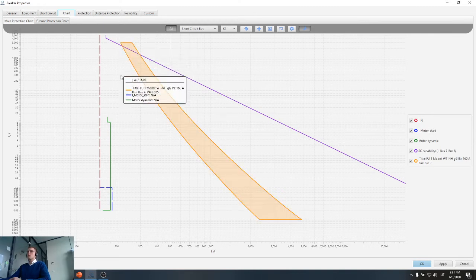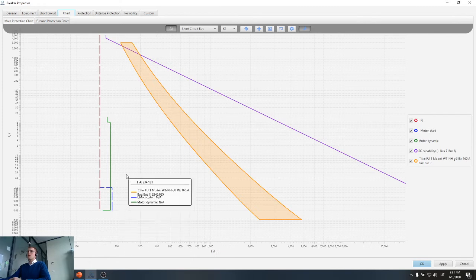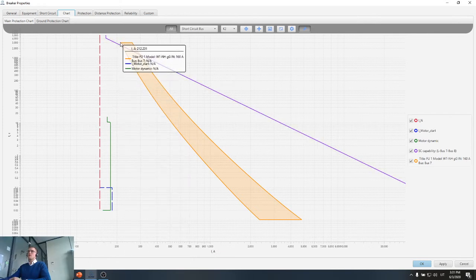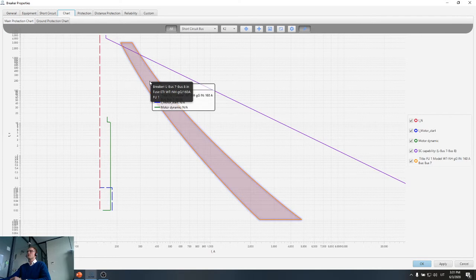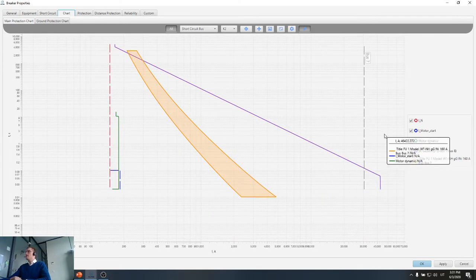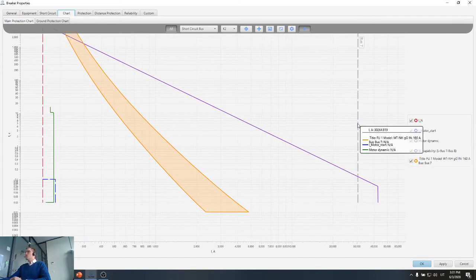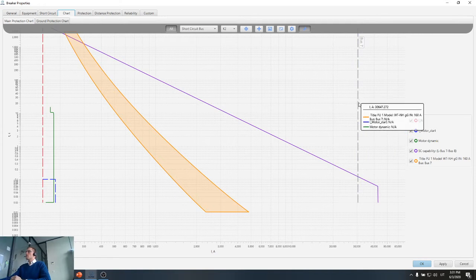So you can go down here. On the lower axis we see that there is current axis. So our fuse current pickup is much bigger than our normal current, which is good. So basically our protection won't trip during normal operation. Here on the right side we have one more dashed line, which is in a gray color, and this dashed line shows a short circuit in the end of the cable. In this case not in the end, but in the beginning of the cable.